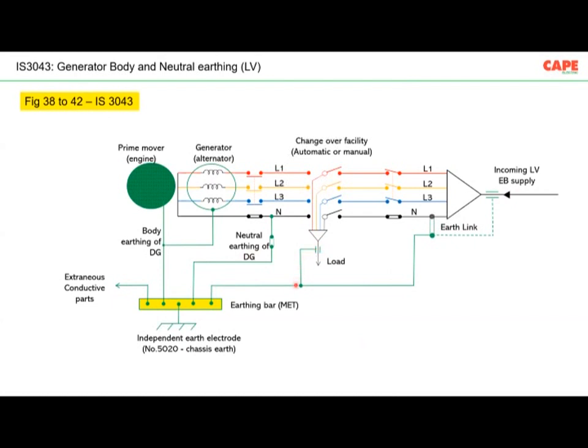Load side protective earth conductor is connected to the same bus bar. The same bus bar is connected to an independent earth electrode with a number 5020. The same bus bar is connected to extraneous conductive parts such as other metallic parts. This is how you are supposed to make an earthing in your installation.